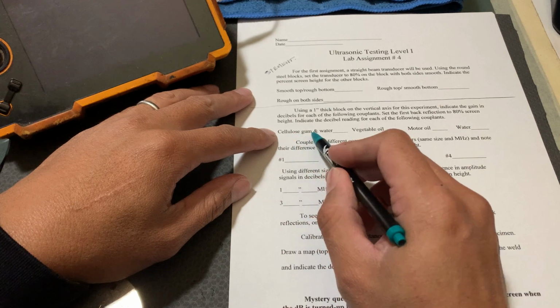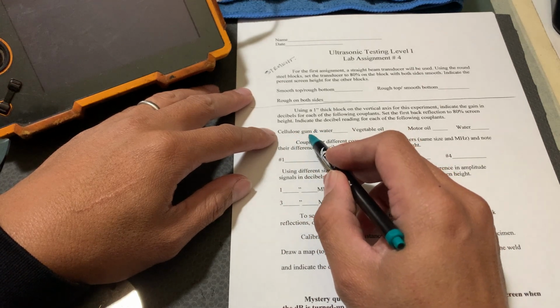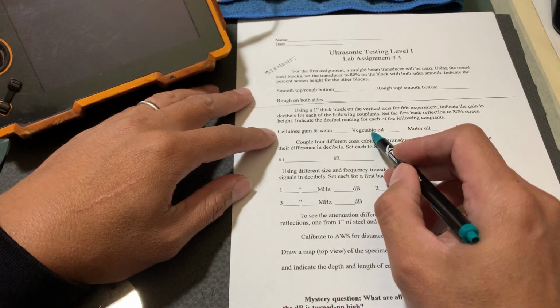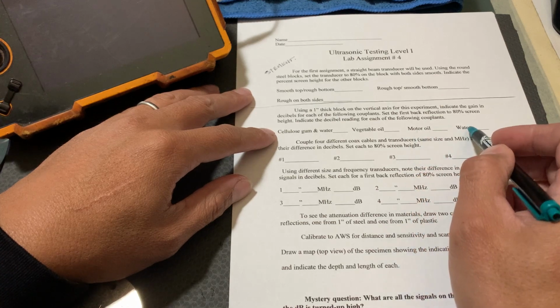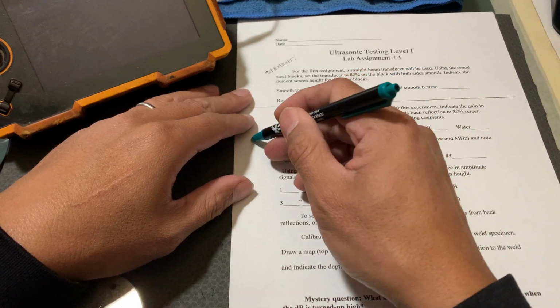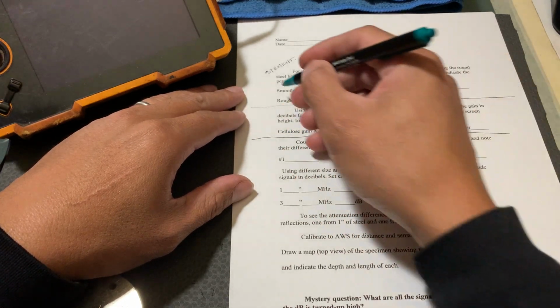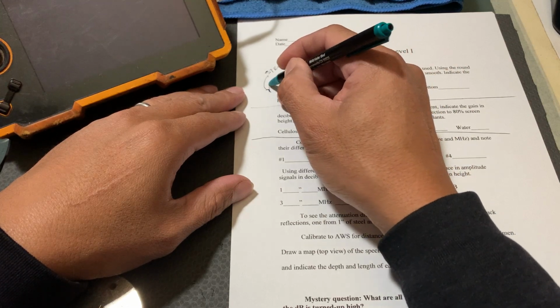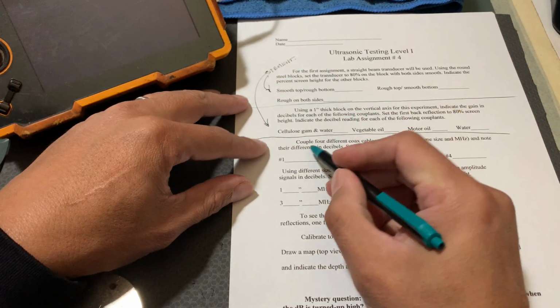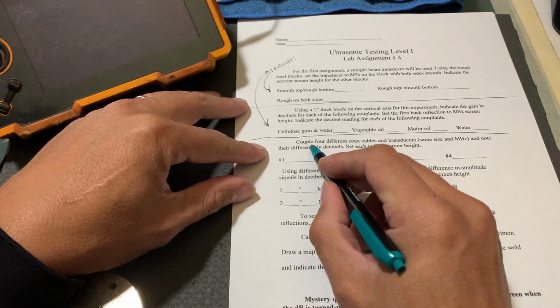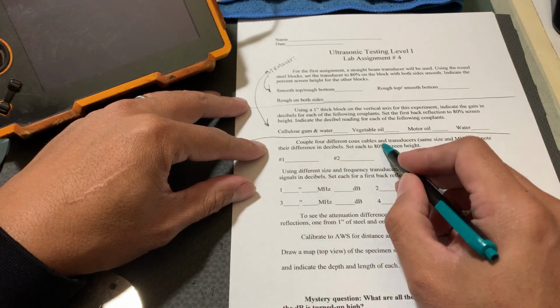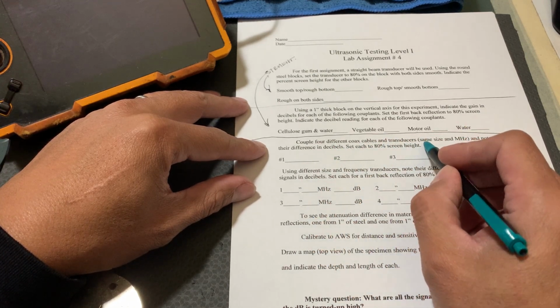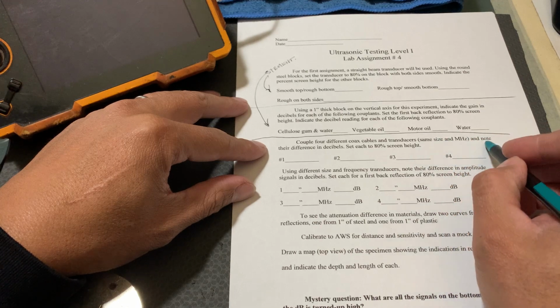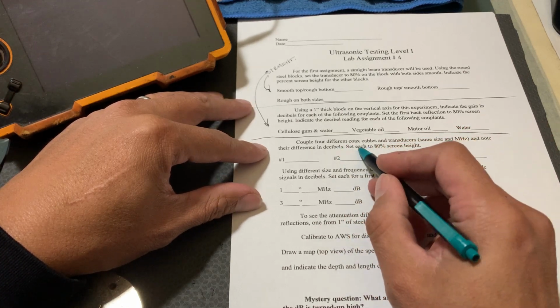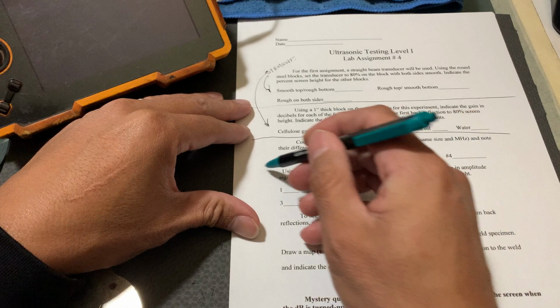So you got cellulose gum water, which is the couplant that we use. We got vegetable oil, motor oil, and water. And this is also a straight beam. The third assignment on this, couple 4 different coaxial cables and transducers, same size and megahertz, and note the difference on decibels. Set each to 80% screen height.